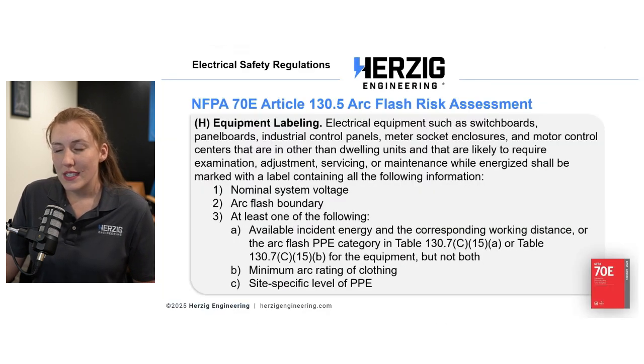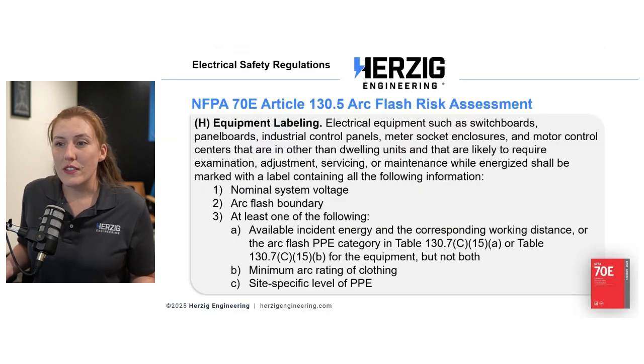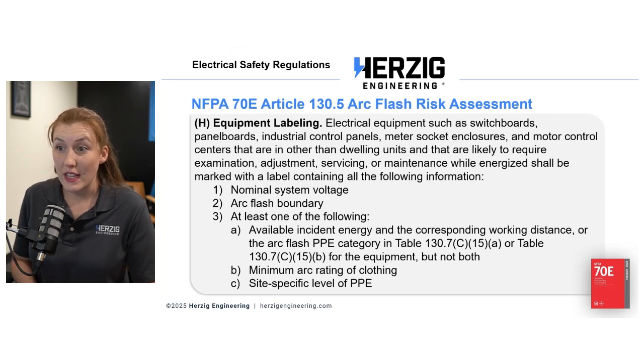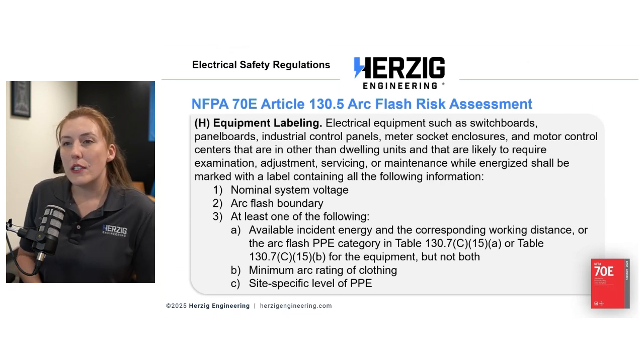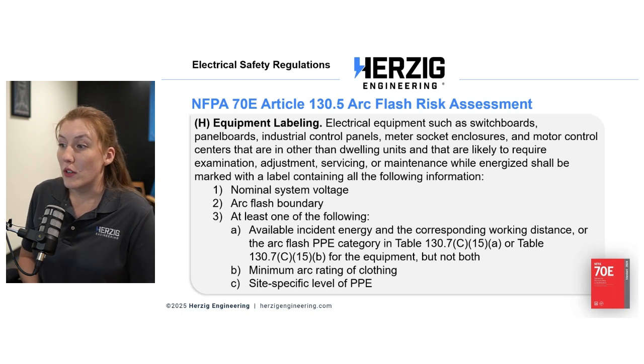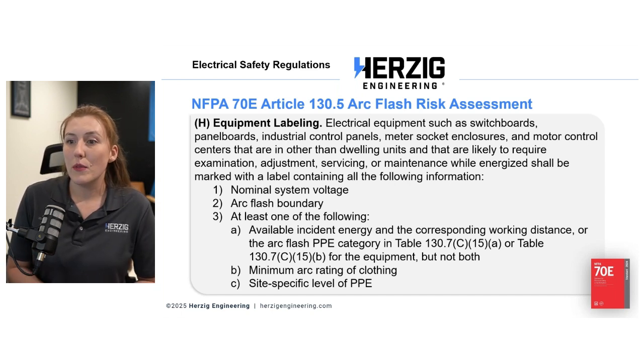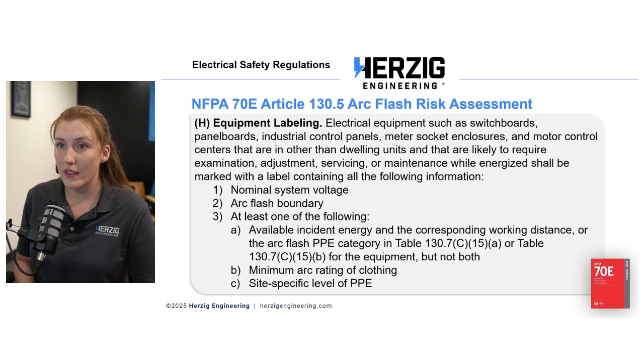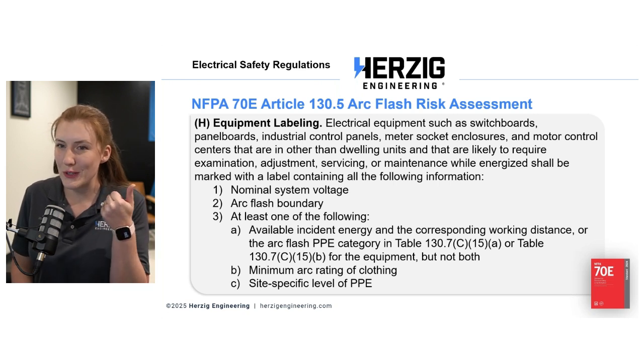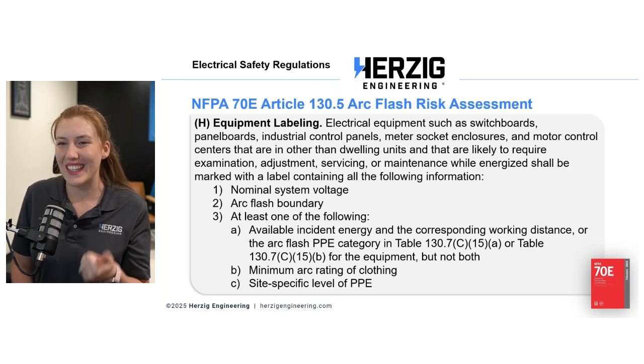Through an arc flash study. So if there's a potential for an arc flash hazard, you do have to have an arc flash study done. That is required. Anything likely to require examination, adjustment, servicing, or maintenance while energized must be labeled with the voltage information. Again, shock hazard is still very prevalent. We're going to get into that.